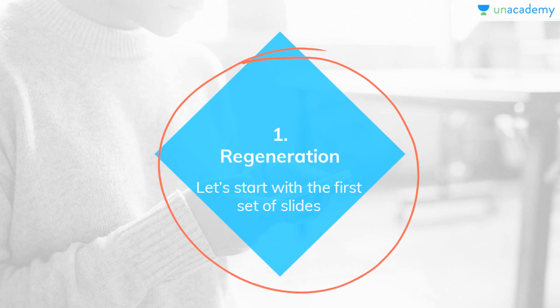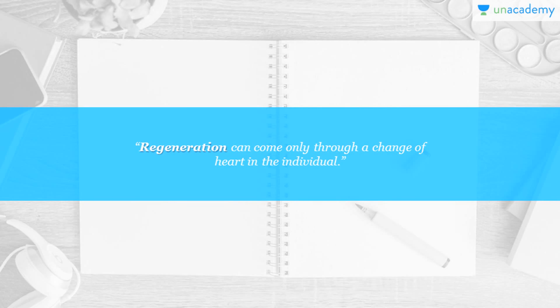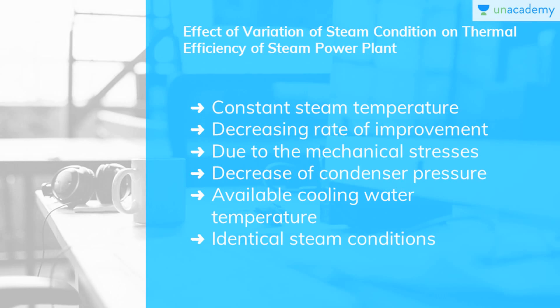Let's move on with our lesson on regeneration. The effect of variation of steam condition on thermal efficiency of a steam power plant: the variation of Rankine efficiency with inlet steam pressure at a constant temperature of 470 degrees centigrade happens at 3 condenser pressures. It is seen that for inlet steam pressure above 100 bar, there is a continuing but decreasing rate of improvement of cycle efficiency.